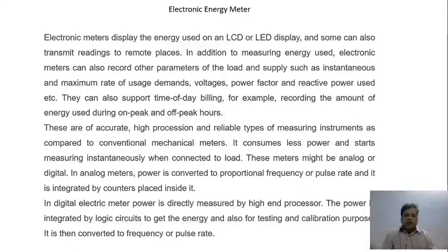Electronic meters display the energy used on LCD or LED display, and some can also transmit a reading to remote places. In addition to measuring energy use, electronic meters can also record other parameters of load and supply such as instantaneous and maximum rate of usage demands, voltages, power factor and reactive power used. They can also support time of day billing, for example, recording the amount of energy used during peak and off peak hours. These are accurate, high precision and reliable types of measuring instruments as compared to conventional mechanical meters.